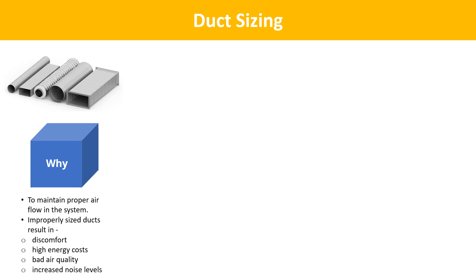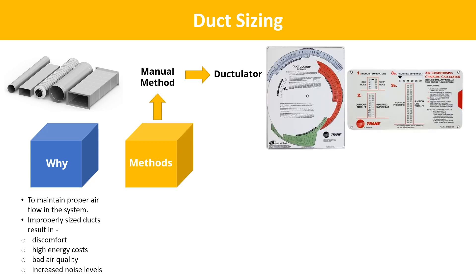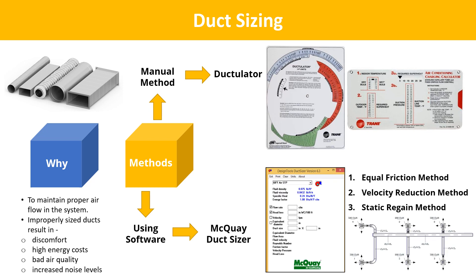The next term is Duct Sizing. Duct systems are designed to properly distribute air throughout a building. Ducts that are not well designed result in discomfort, high energy costs, bad air quality, and increased noise levels. Choosing the right size duct is critical to maintain proper airflow in the system. For manual duct sizing, a ductilator is used — the McQuay Duct Sizer is the most widely used. Methods employed to calculate the right size of duct include the Equal Friction method, Velocity Reduction method, and Static Regain method.